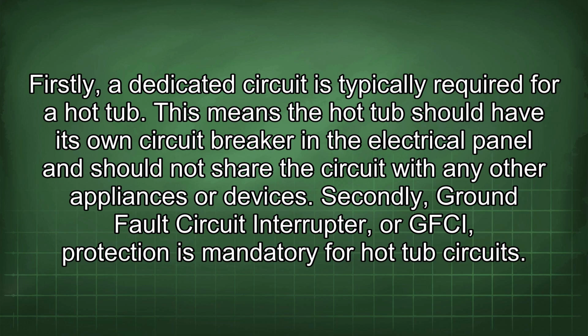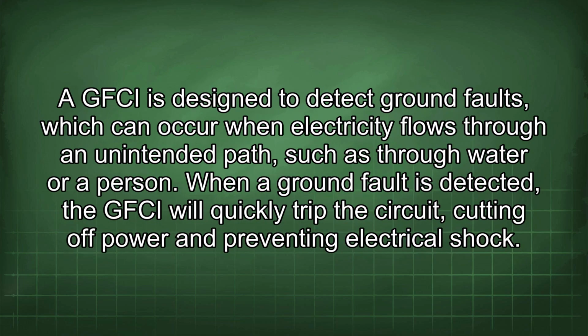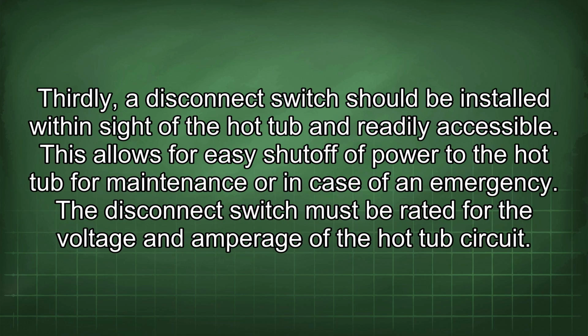Secondly, ground fault circuit interrupter, or GFCI, protection is mandatory for hot tub circuits. A GFCI is designed to detect ground faults, which can occur when electricity flows through an unintended path, such as through water or a person. When a ground fault is detected, the GFCI will quickly trip the circuit, cutting off power and preventing electrical shock. Thirdly, a disconnect switch should be installed within sight of the hot tub and readily accessible. This allows for easy shut-off of power to the hot tub for maintenance or in case of an emergency. The disconnect switch must be rated for the voltage and amperage of the hot tub circuit.